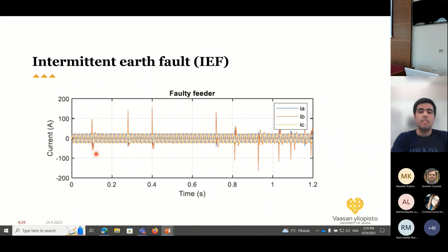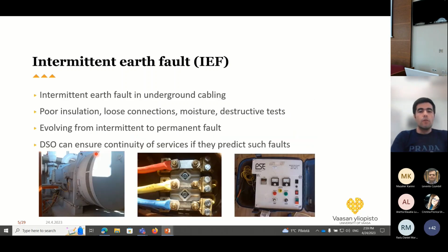However, some researchers are searching for a mathematical solution. Maybe it wouldn't be that accurate, and machine learning techniques will be helpful in this situation. So in this study, we have recently started conducting research in this regard. Intermittent earth fault is an intermittent connection of conductors to the ground, and it is common in underground cabling. The main reasons for intermittent earth fault can be poor insulation, loose connection, moisture, and destructive tests.